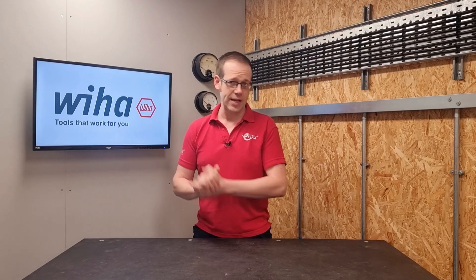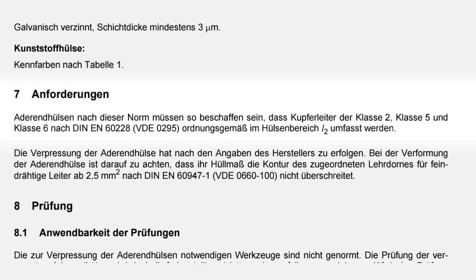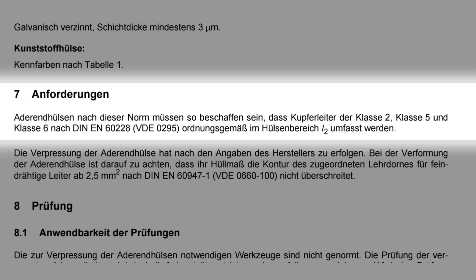We actually need to dive into a German standard rather than a British standard for more information — namely DIN 46228-4. Now my German is not all it should be, and so I've relied on Google Translate to help me with this. In section 7 we read: "Anforderungen — Aderendhülsen nach dieser Norm müssen so beschaffen sein, dass Kupferleiter der Klasse 2, Klasse 5 und Klasse 6 nach DIN EN 60228 ordnungsgemäß im Hülsenbereich L2 umfasst werden."